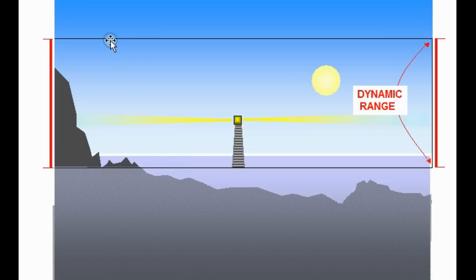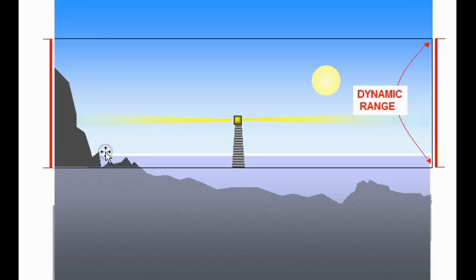Now our analyzer, like all other analyzers, has so much dynamic range. The dynamic range dictates the minimum level we can see and the maximum level we can see. So our signals need to reside in this window. We cannot change the height of this window, but we can move it using the attenuator.